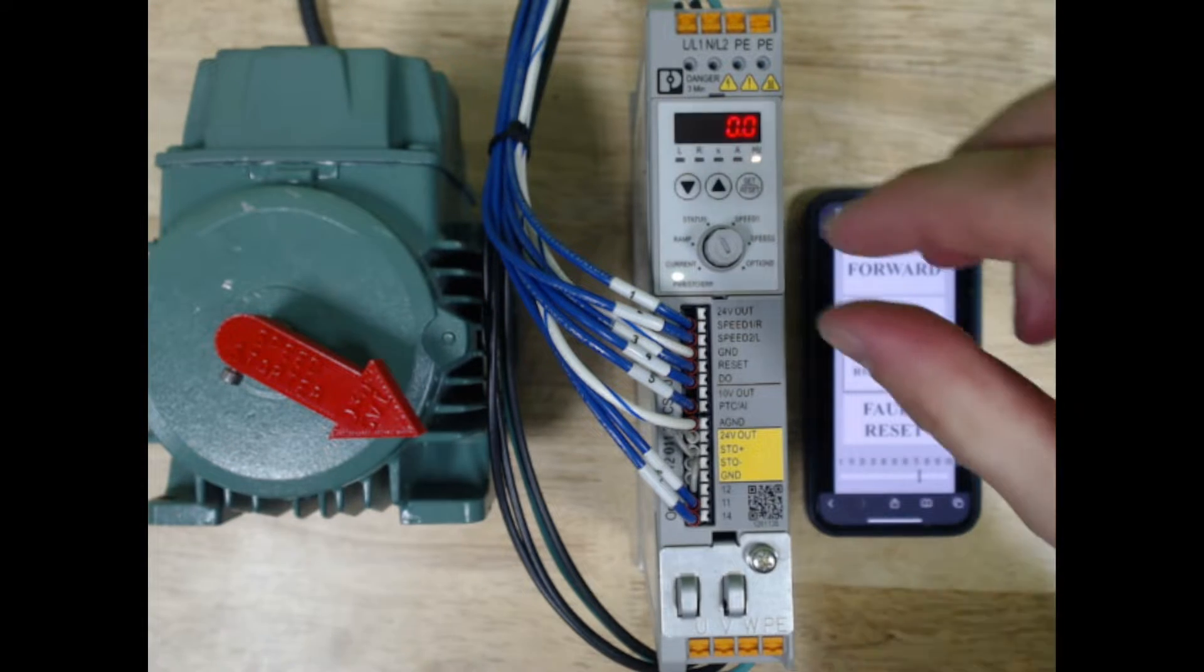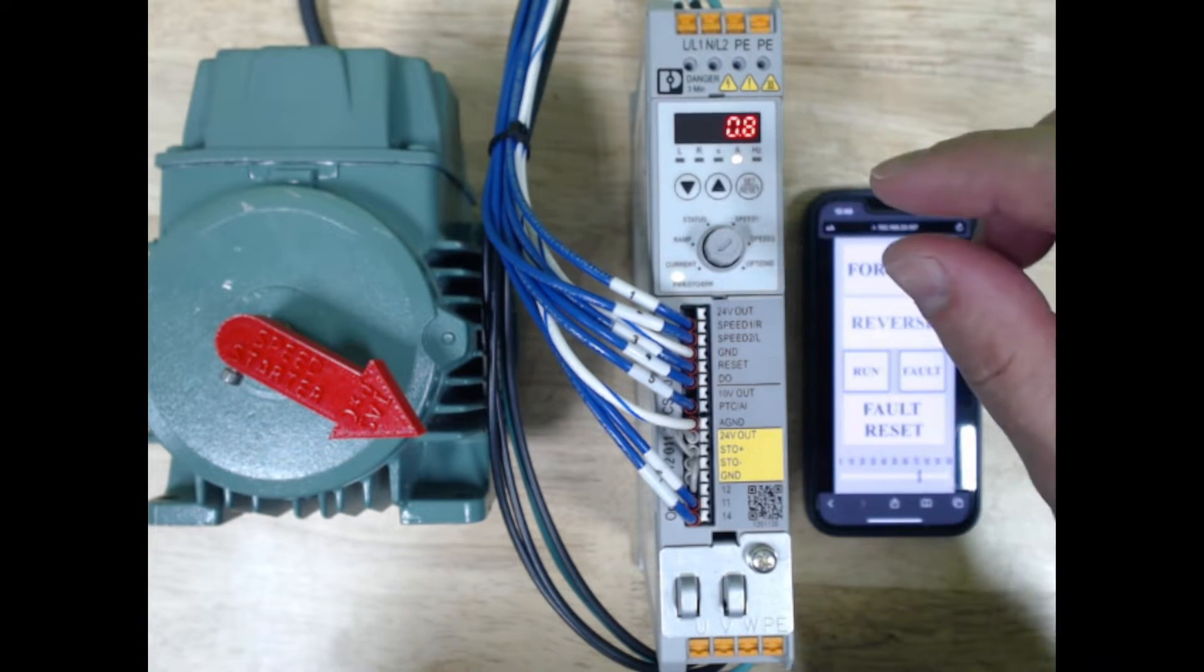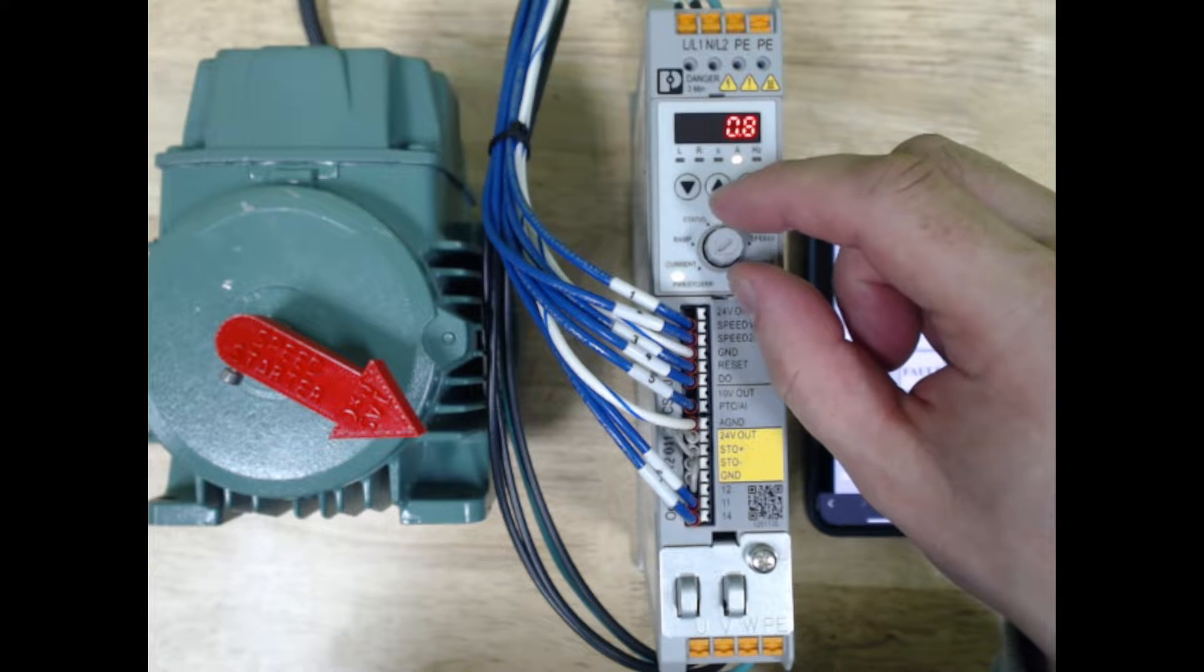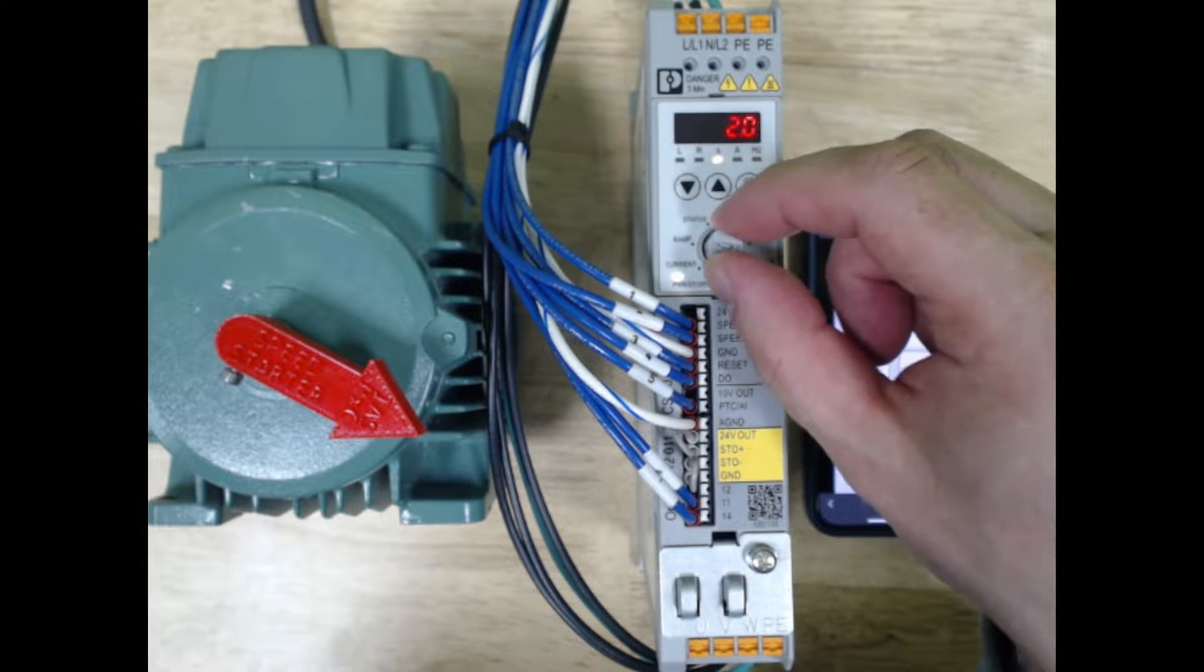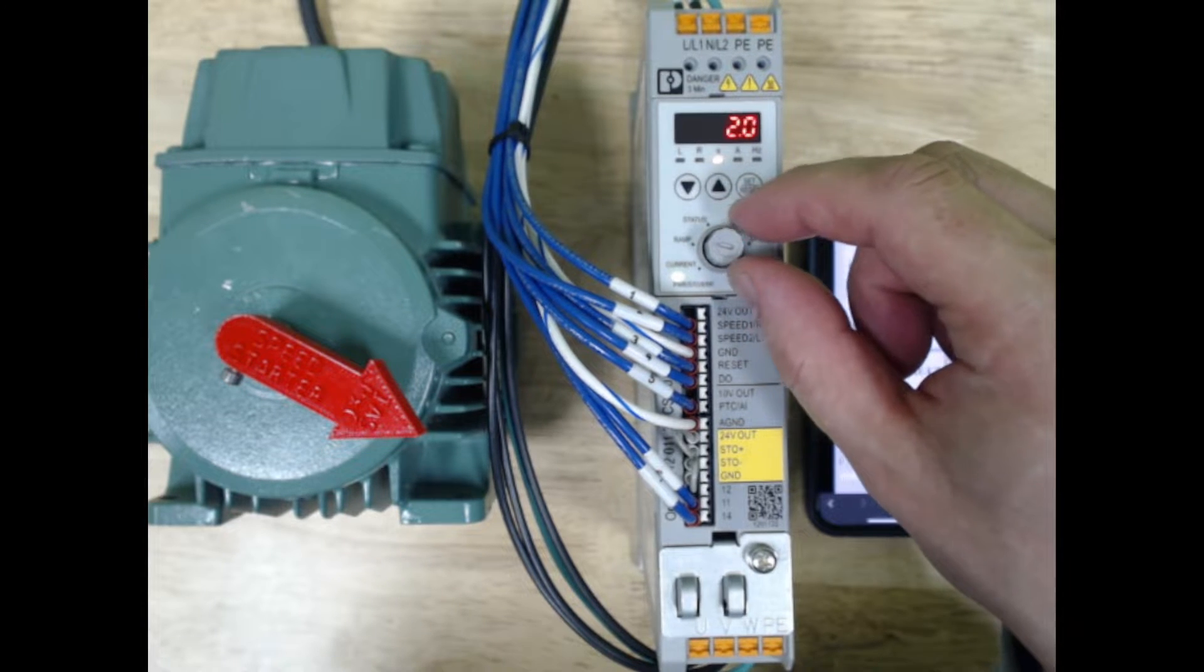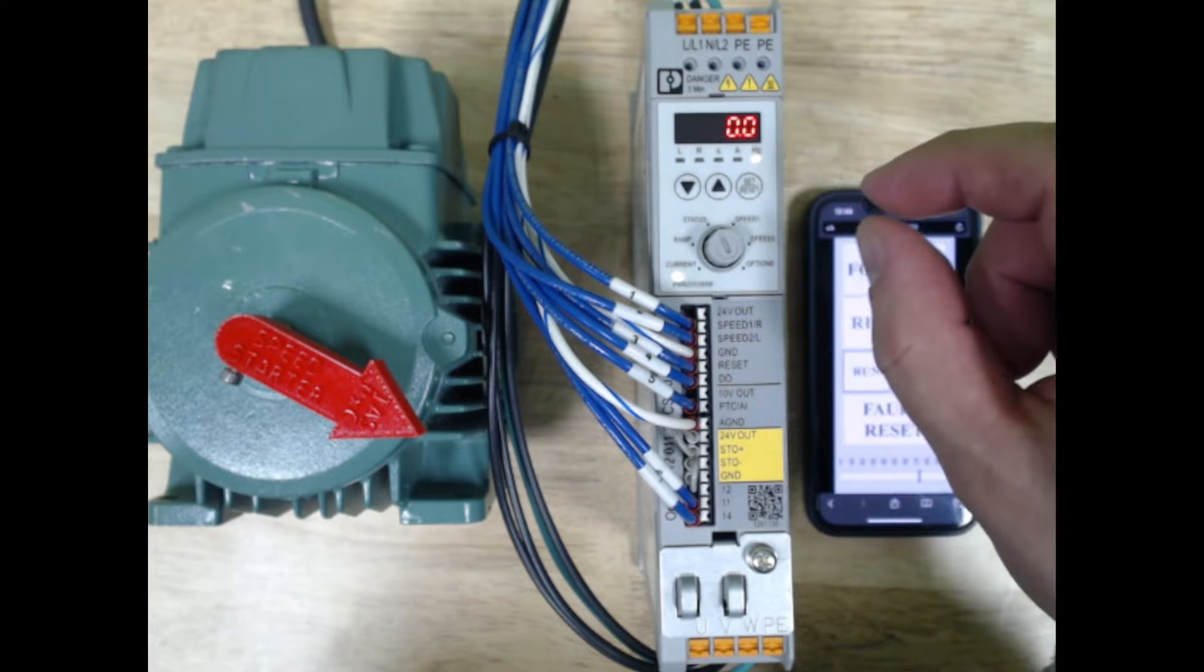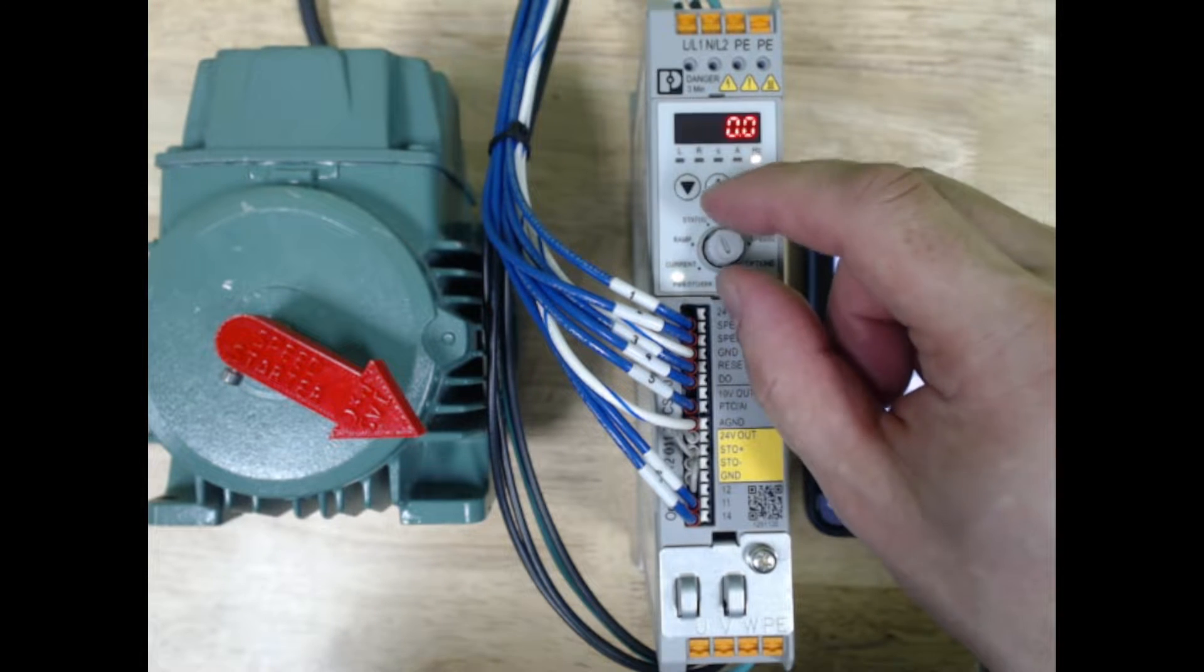Let's go through some of these options here. If we scroll all the way to the left, we get the current. That's the current of the motor that you'll find on the nameplate. The next button is ramp. That's your ramp time in seconds from zero speed to full speed. The status will give you the hertz when running.